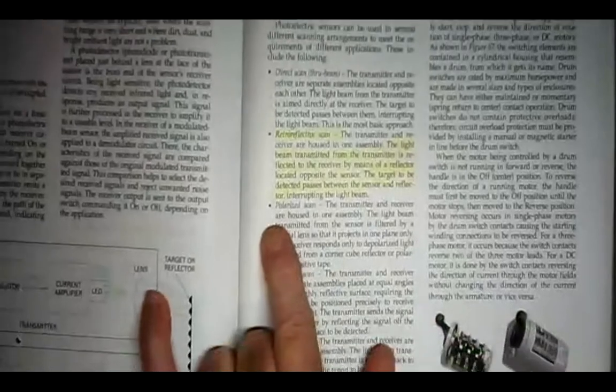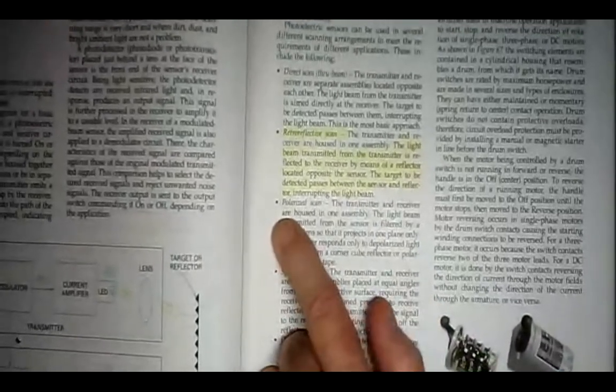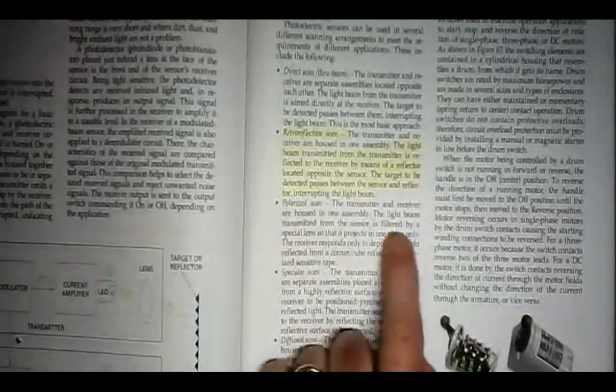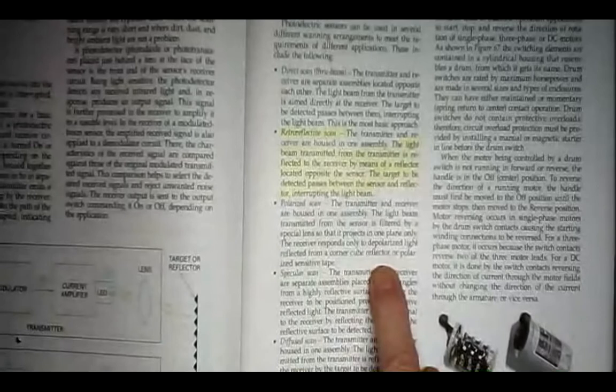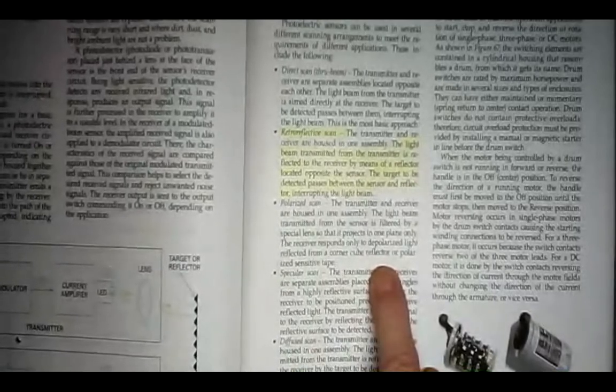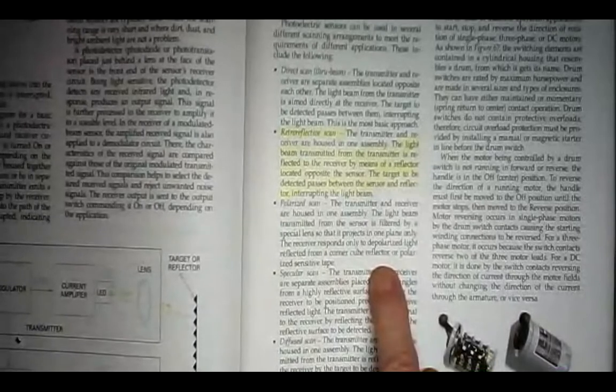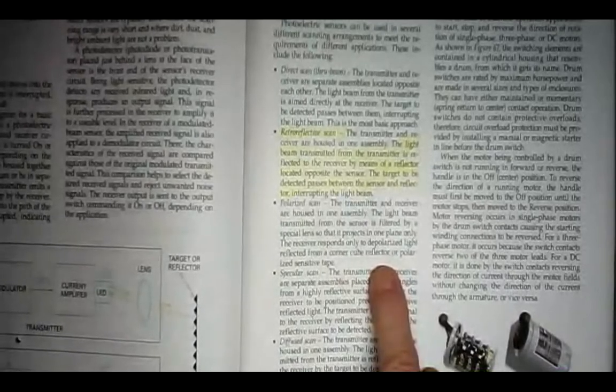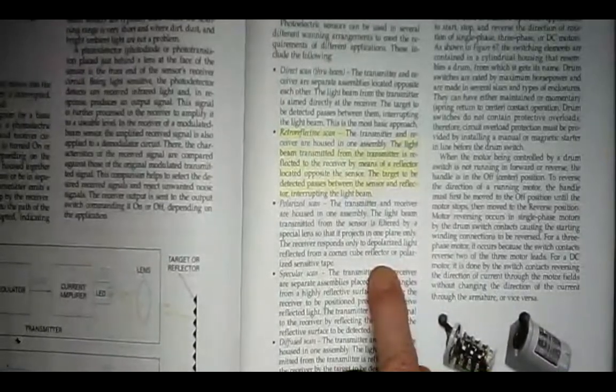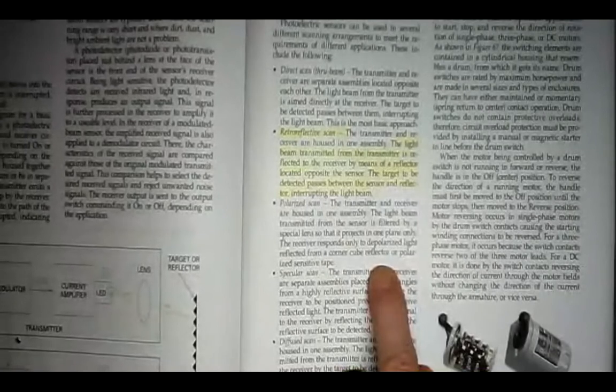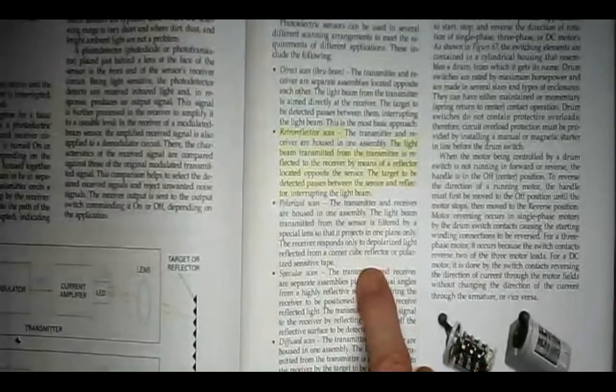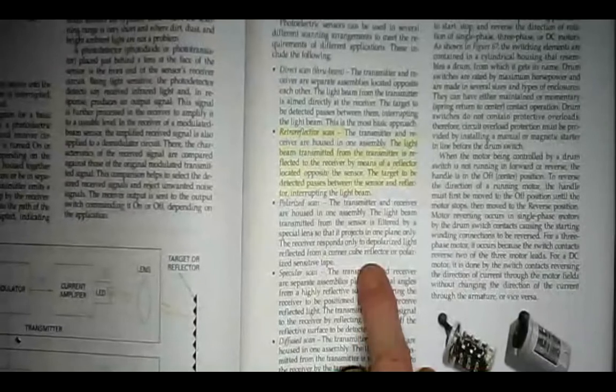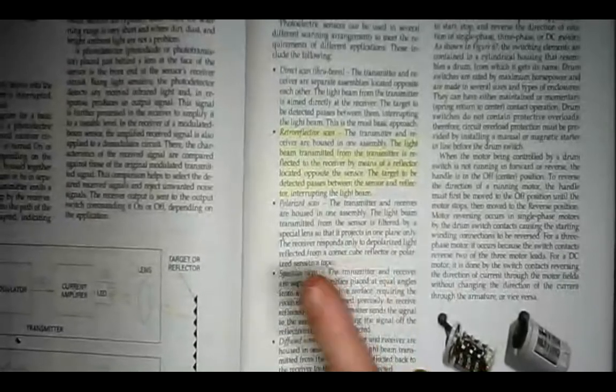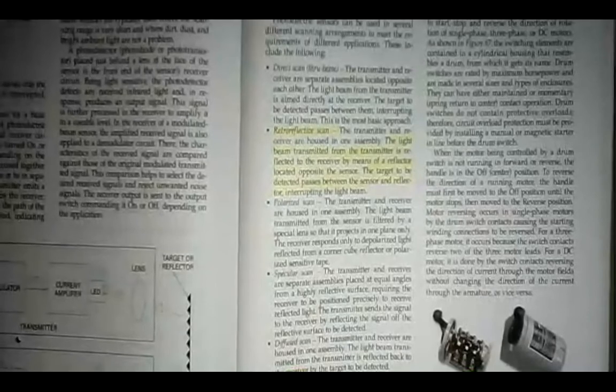Polarized scans, they're kind of clever. It has a prism instead of a reflector so that the light comes out and it's oriented either horizontal or vertical. Let's say it's vertical and it comes out. When it hits that prism, it bounces back and it changes the polarity to a horizontal bias. That way, if something shiny does go by, if a metal box goes by, it doesn't reflect the beam back to the receiver and fool the receiver into thinking nothing's there. It doesn't change the orientation of the beam. The polarized reflector or prism does. So it knows that there's something there. Okay.